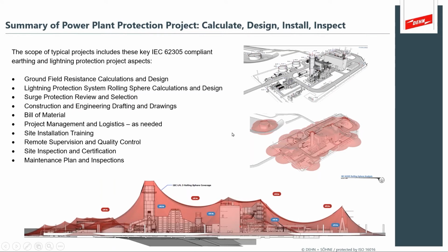So when we're conducting these types of projects, these are very complicated, extensive projects. We take a very careful look at the grounding. We help design the ground field. We can calculate the earthing measures that have to be installed. We take a very careful look at the lightning protection rolling sphere coverage calculations around the plant to make sure that all of the structures fall within a protection that might be offered by the actual lightning rods.